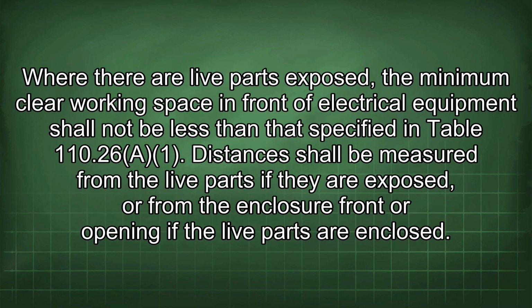Where there are live parts exposed, the minimum clear working space in front of electrical equipment shall not be less than that specified in Table 110.26(A)(1). Distances shall be measured from the live parts if they are exposed, or from the enclosure front or opening if the live parts are enclosed.